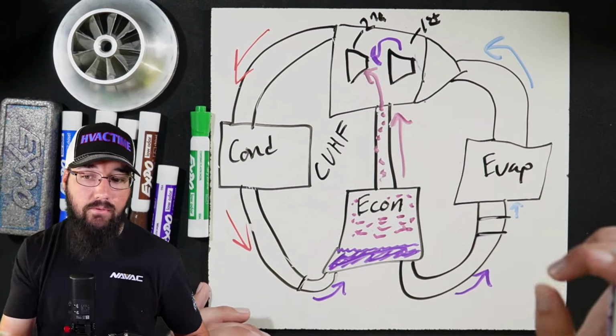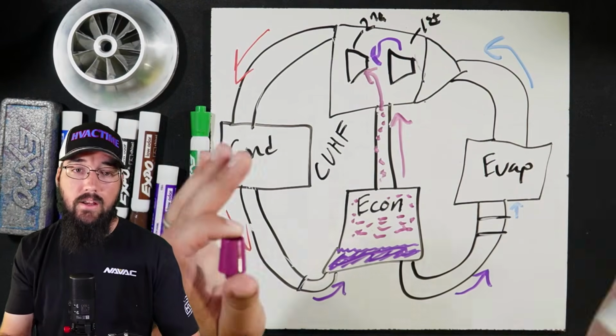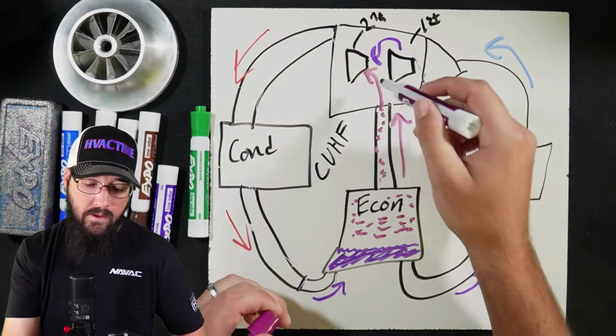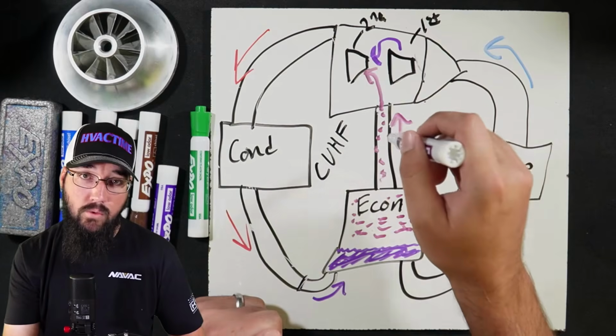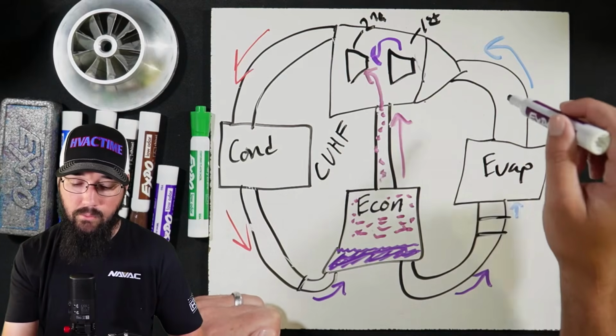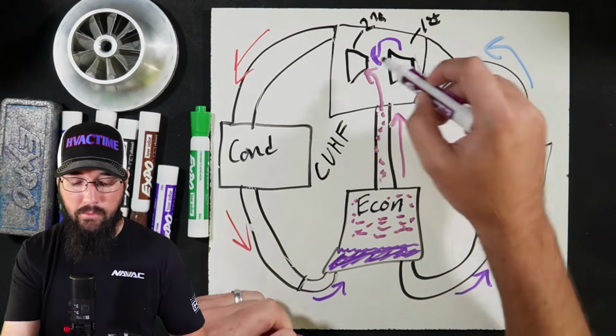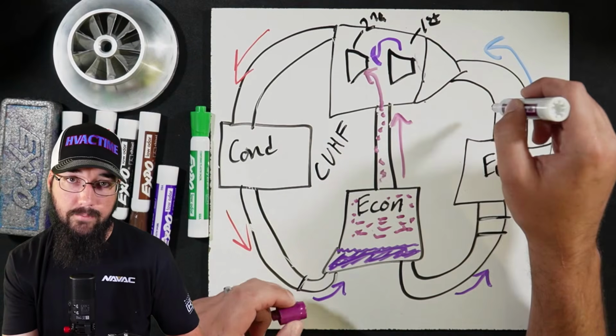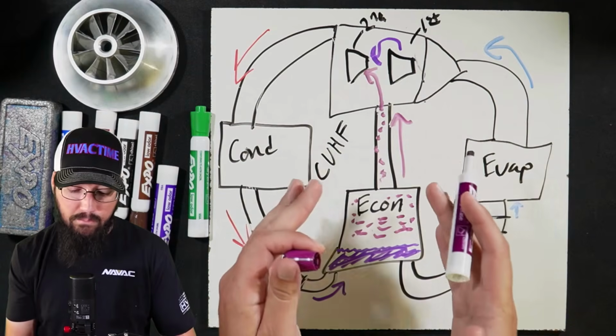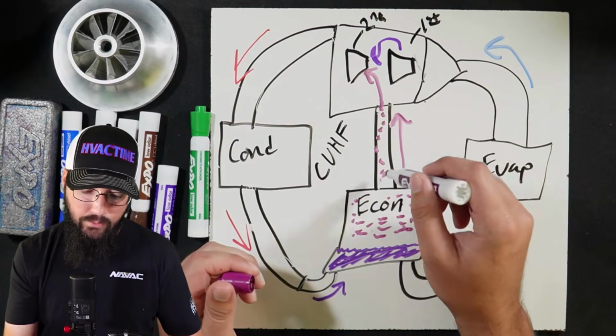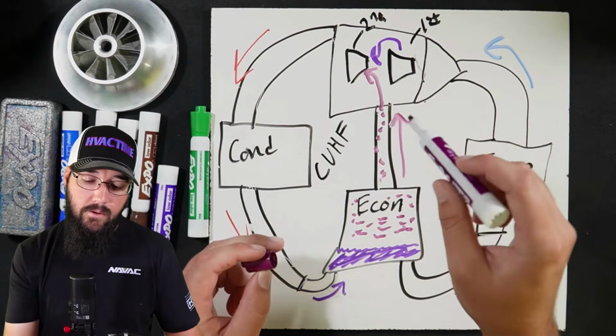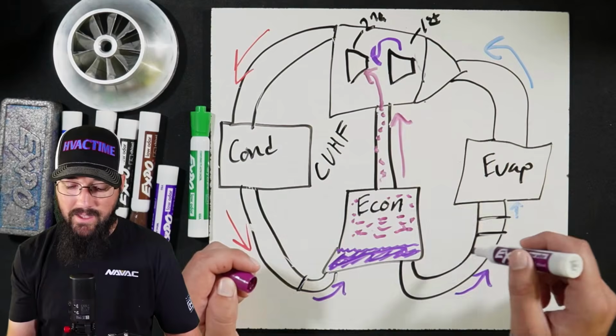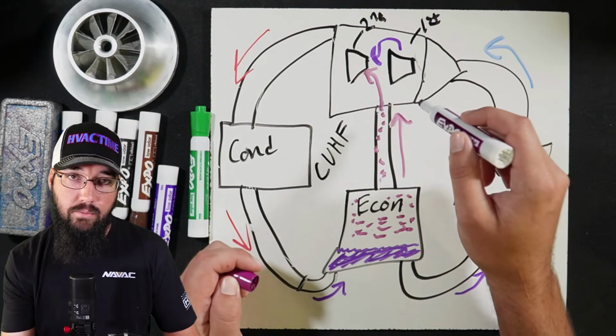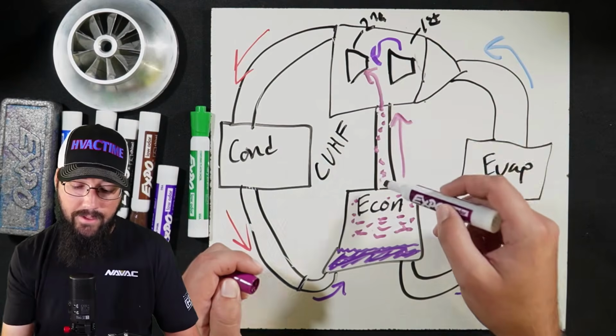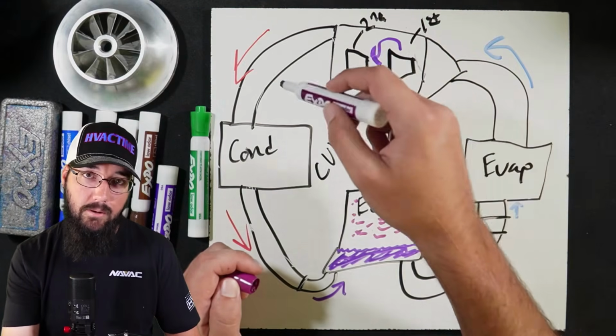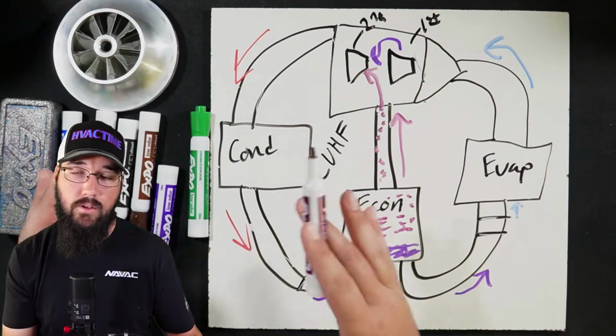And because of that very fact, we're only going from medium to high pressure. The compressor has to put less work, less horsepower into this refrigerant than it would have had to do if all of that vapor went all the way back in through the suction as a low pressure. This is the fundamental purpose of that economizer: we are reducing compressor load by not having the compressor cycle 100% of the charge as low pressure gas back to a high pressure. We can take some of that as medium pressure, step it up to high pressure, and reduce the total work the compressor has to do in the end.